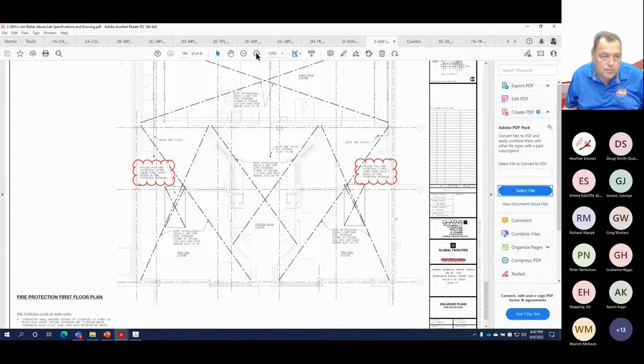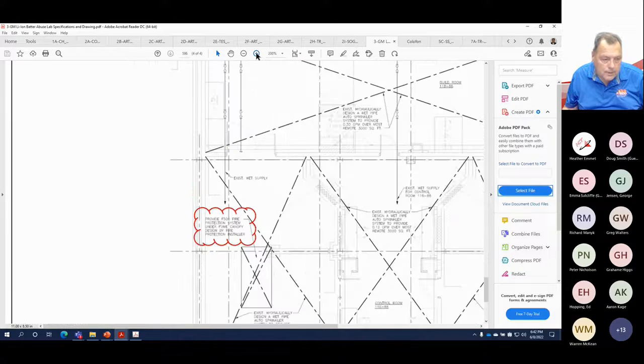If I blow this up a little bit, we can see that we're providing an F500 fire protection system under the flume. So we did a design here using a sprinkler density of 0.2 gallons per minute per square foot, a proportioning rate of 3%.